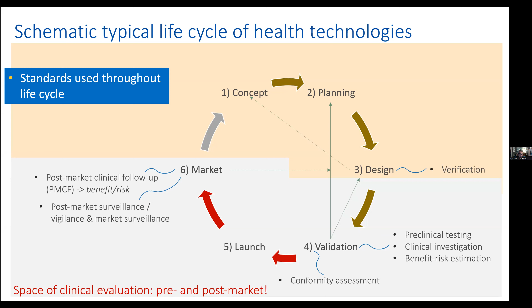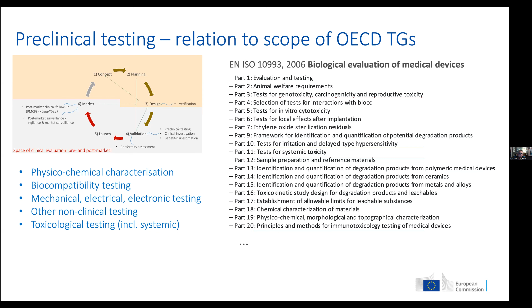Now, what is maybe closest to the WNG, I thought, was tests for biological evaluation, for instance toxicity, also genotoxicity, irritation, etc. And you see here, this is just a part of the ISO standard 10993 on biological evaluation. There is also, and that's interesting, an example that TG 439 was fed into the ISO standard. It was first a test guideline for skin irritation that then became an ISO standard with, of course, a different SOP. But I think that example is closest to what you're discussing, not standards on quality management systems and so on.